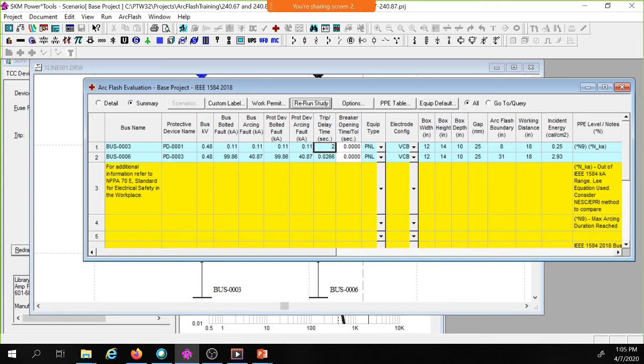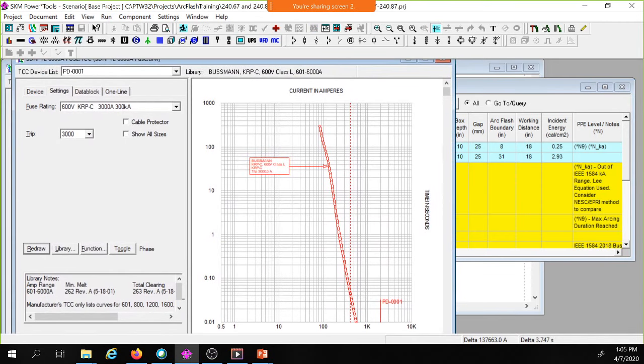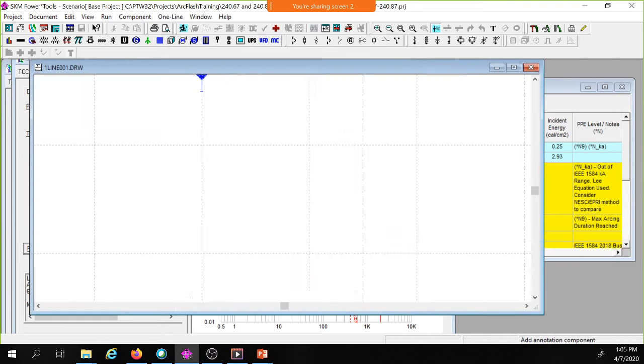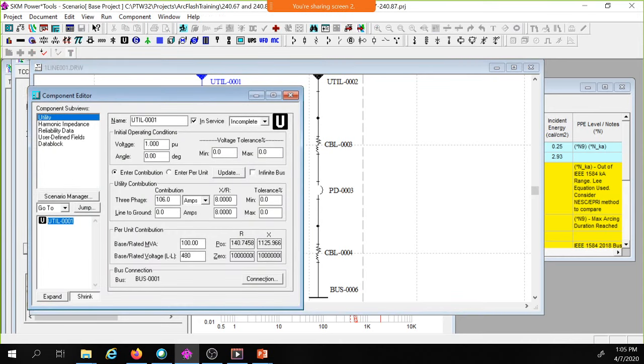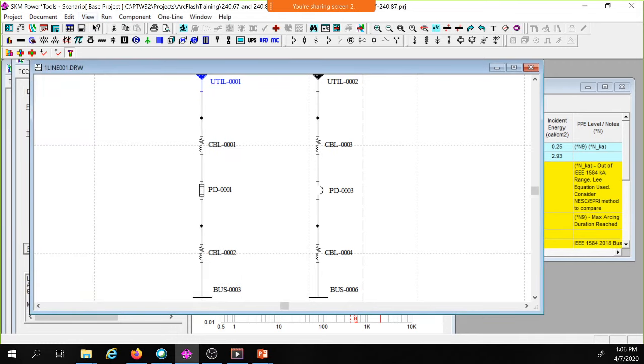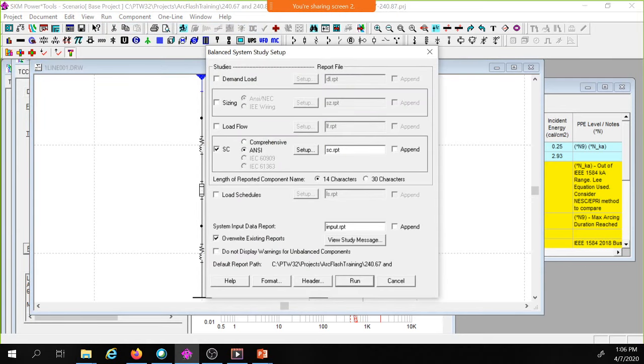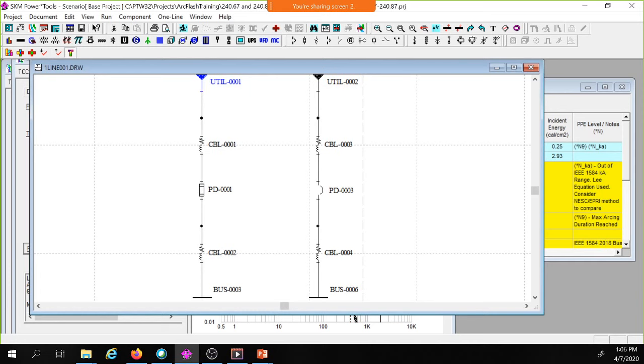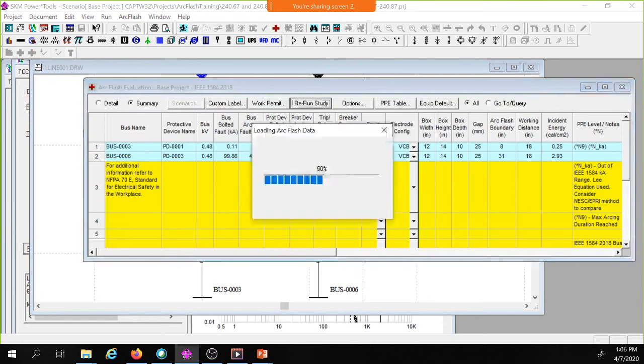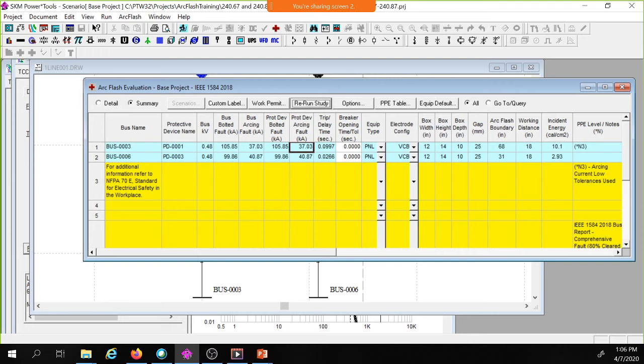Now my protective device is 0.11, 480 volts, 0.25. Let's go back to this. Oh, wait a second. Go back to my one-line diagram. I think I screwed up. Yep, I have 106 amps. I have 106,000 amps. Boy, see, that's what live TV does to you. Rerun the study. Now I'm right: 37,000 amps.